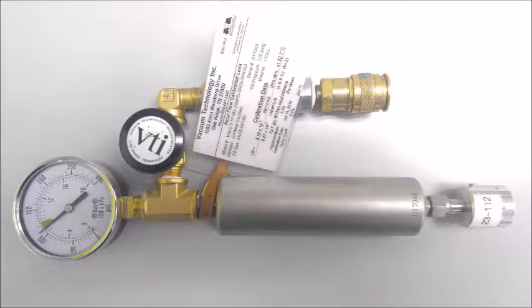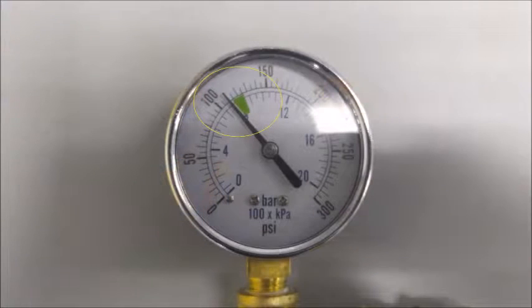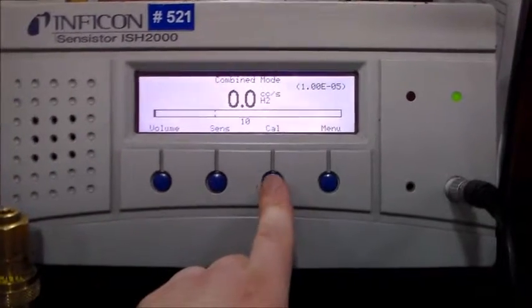The ISH2000 uses a reference leak value to calibrate in order to get the correct leak value for proper test results. This calibration must be performed on a daily basis. To calibrate the ISH2000, you must gather a reference leak instrument from your supervisor or lead, or get one from manufacturing engineering. Verify the reference leak is pressurized to within the green area on the gauge. If it is not, you must get one that is before proceeding.